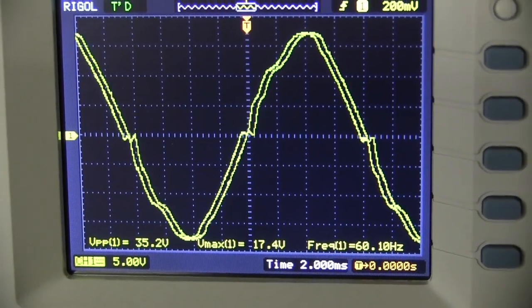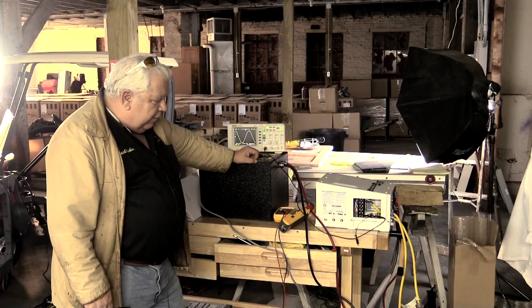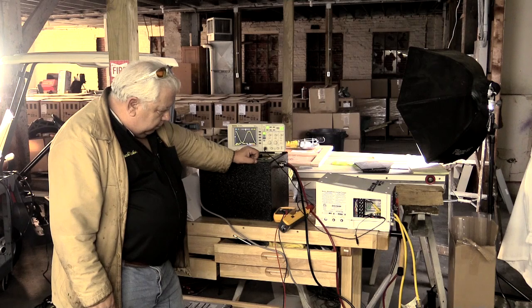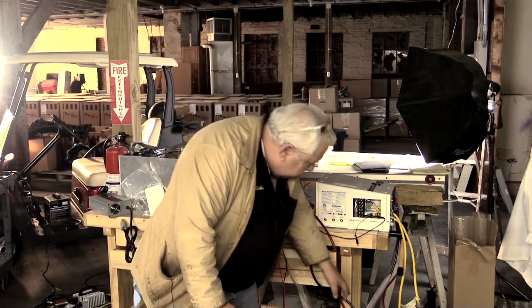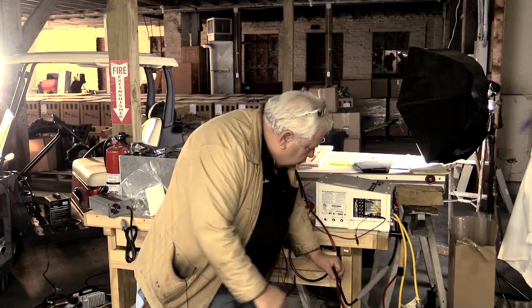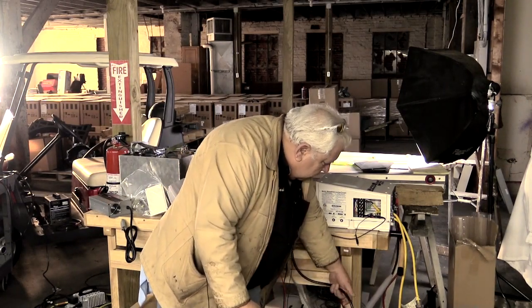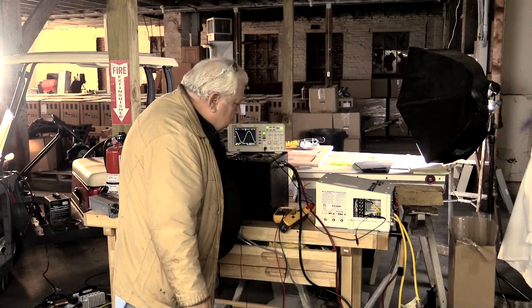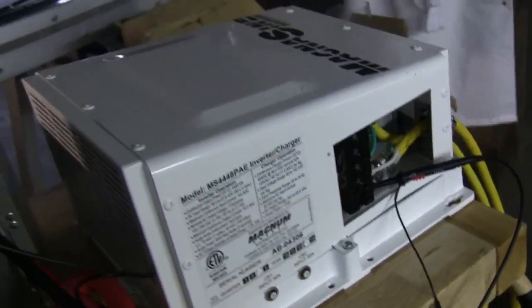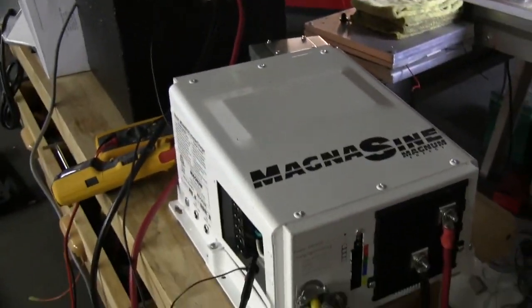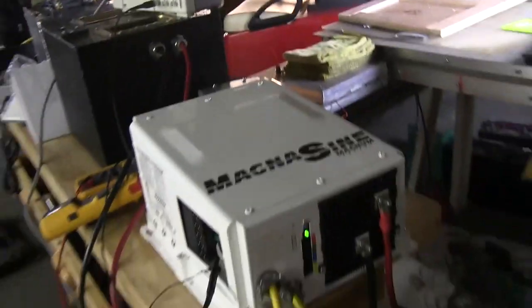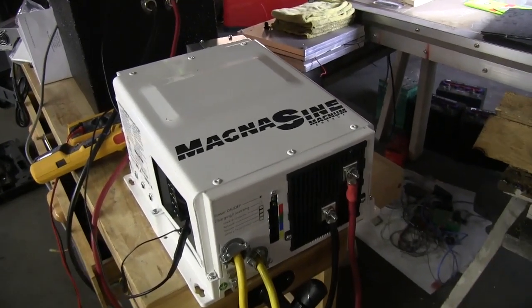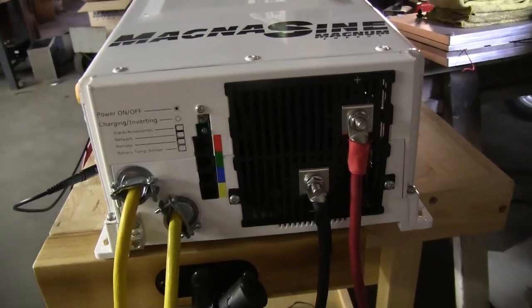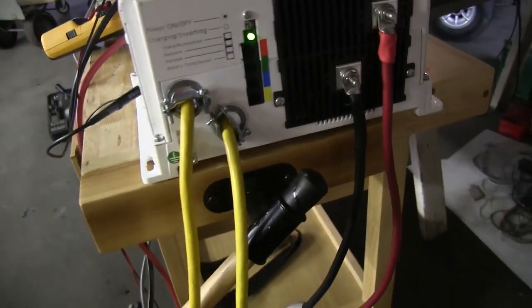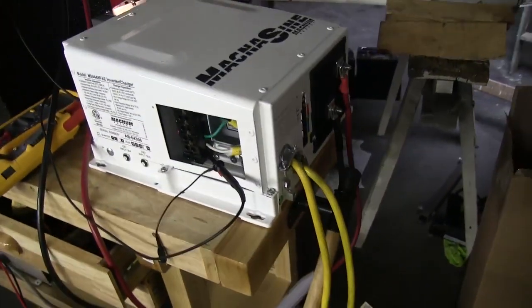This is a MagnaSine inverter, and it's designed to be used off-grid. I have it connected to the batteries with some cables using these Tweco welding cable connectors, so I can easily connect and disconnect them. This is actually an inverter charger and battery backup supply. Right now I've got it wired up, it works, and one of the things I like about this is it's ambidextrous. It's equally adroit with 120 volts or 240, either in or out, or from battery.